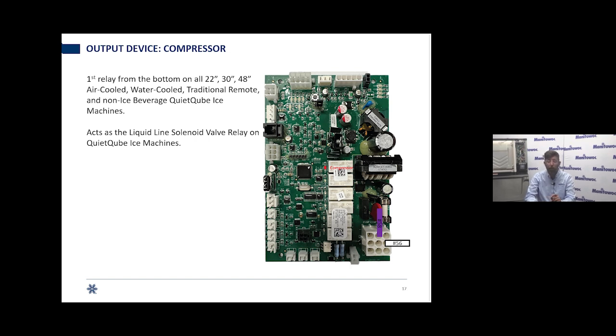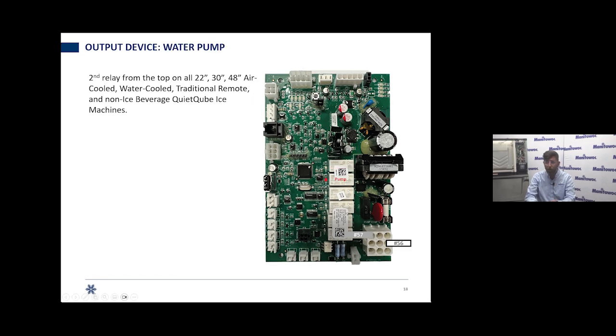We energize this during refrigeration startup, freeze, and harvest. All right, our water pump. It's the second relay from the top, all 22-inch, 30-inch, 48-inch air-cooled, water-cooled, traditional remote, and again, the non-ice beverage QuietQube ice machines. So what we're looking for at that point is, with the ice beverage, this board's going to be turned horizontal. You just got to get your perspective, look at your diagram, and you'll be able to see where everything is. And also on the sides of the relays, it is labeled which one is which.